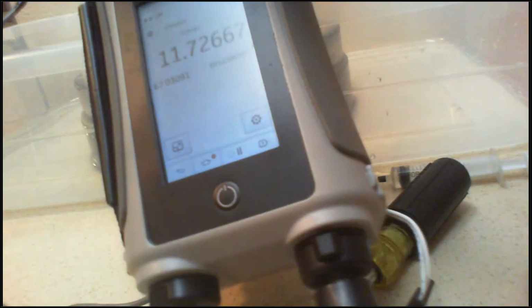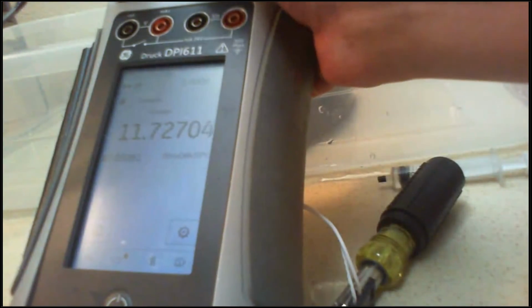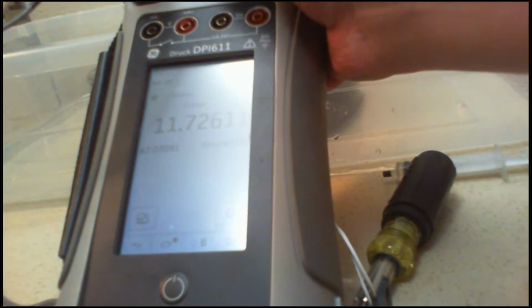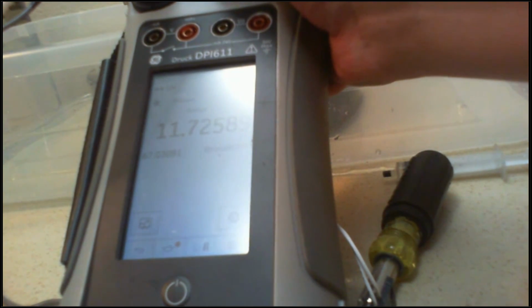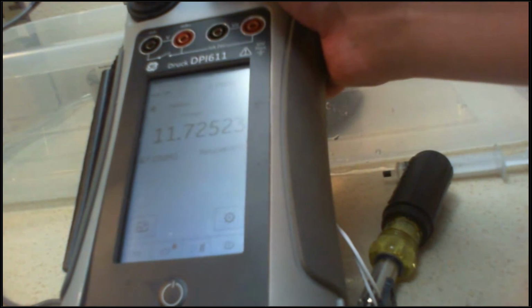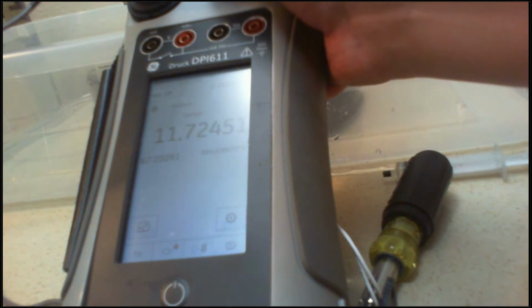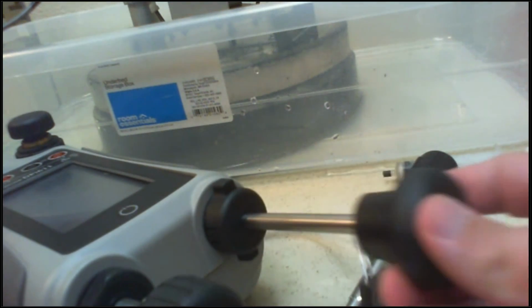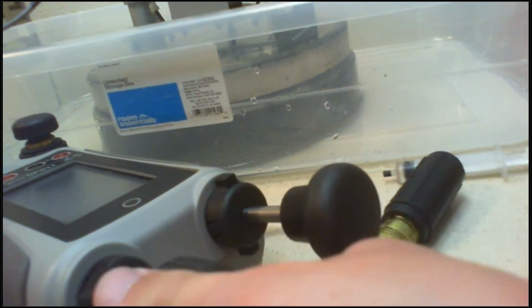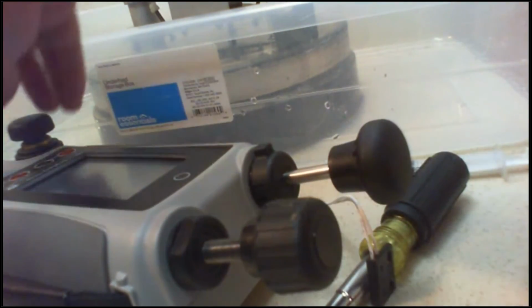Yeah, great question. So I used, let me try to adjust my camera and not awkwardly show off half the hotel kitchen. Make this a little bit bigger. I used this device. Oh, sorry, I know it's cramped on this table, which is a Druck DPI 611. It was one of their newer models of calibrators, but all it really is, it's a PT with a screen, but it's a really, really, really accurate PT with a screen that you can use to reference pressure. And then on the bottom of it, which is why I've had some issues showing it all on camera, you've got a pump that can pump up pressure. You've got a fine-tune adjustment, and you've got a pressure relief valve.